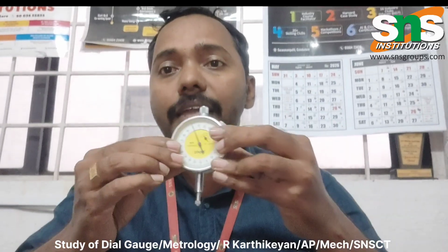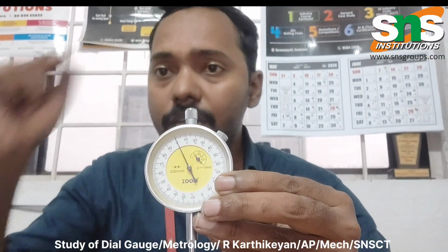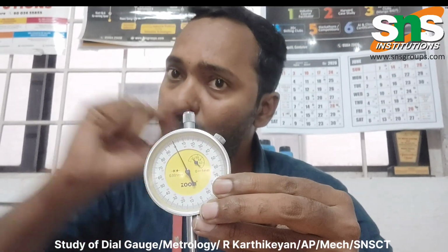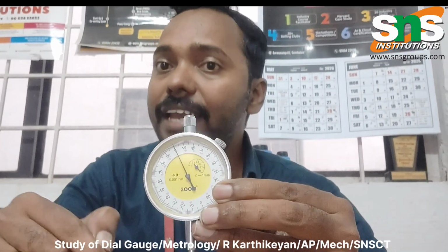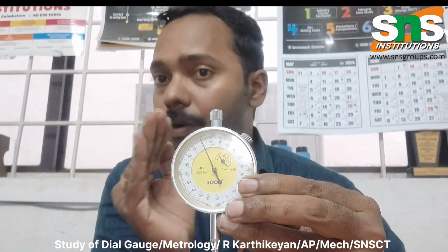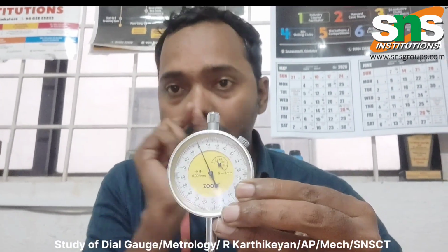So see the dial gauge, that dial indicator moves in the clockwise direction and the anti-clockwise direction. For example, if it is a peak, the dial indicator moves clockwise. But if it is a valley, the dial indicator moves from clockwise to anti-clockwise direction. So anti-clockwise and clockwise are the two very important directions only. Anti-clockwise means you put the symbol minus. Clockwise means you put the symbol plus. This is a simple experiment to measure the flatness of the object.